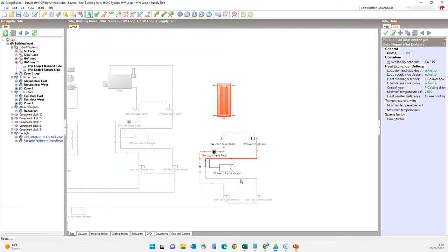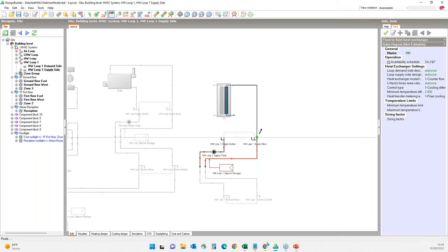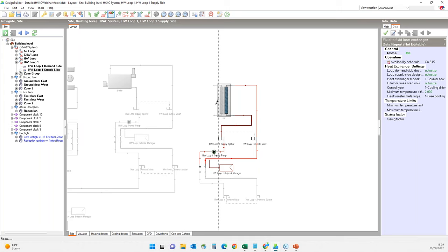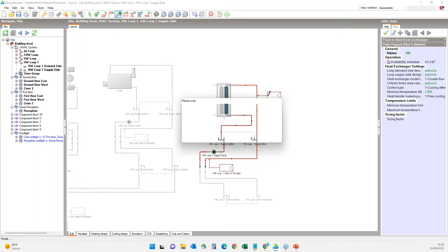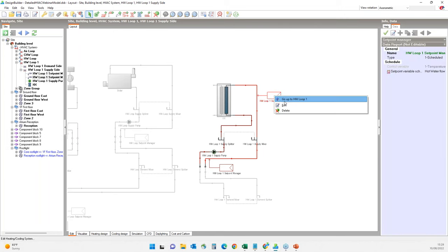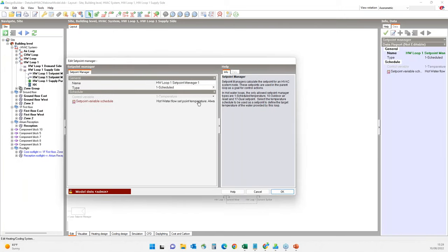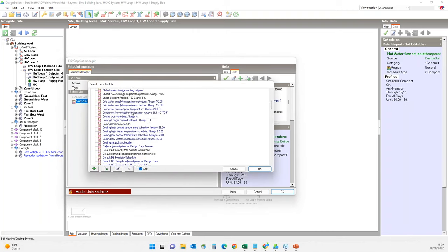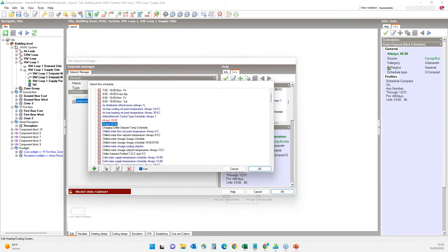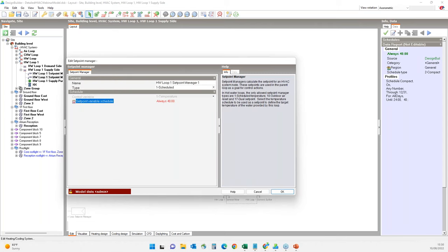I'll connect the supply side. This type of heat exchanger requires a separate setpoint manager on the supply side outlet. I'll add and edit this setpoint manager and change its temperature to 40 degrees — this is a schedule I created beforehand, and 40°C is a typical temperature used for radiant heating. I'll select the same setpoint manager for the setpoint after the supply mixer as well.